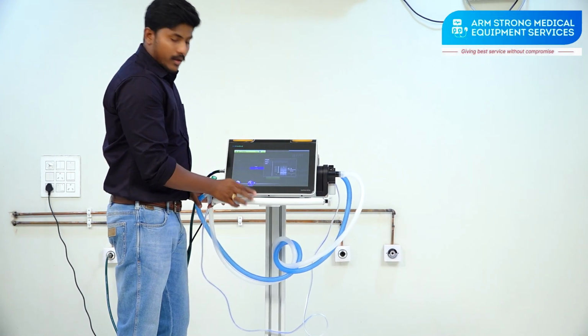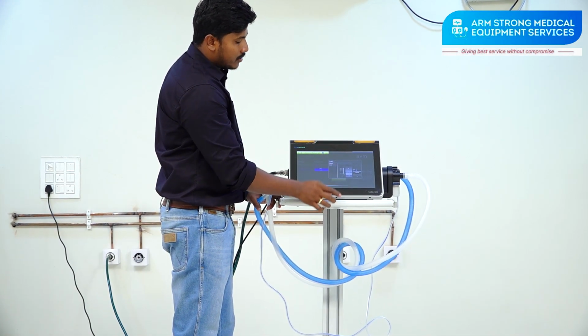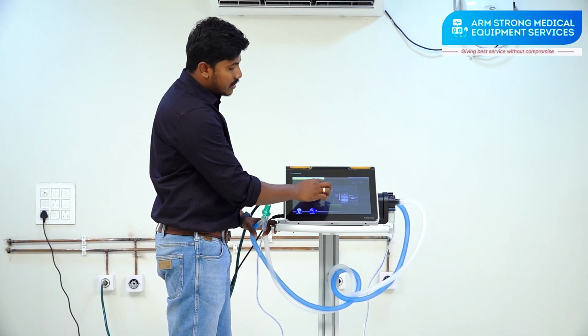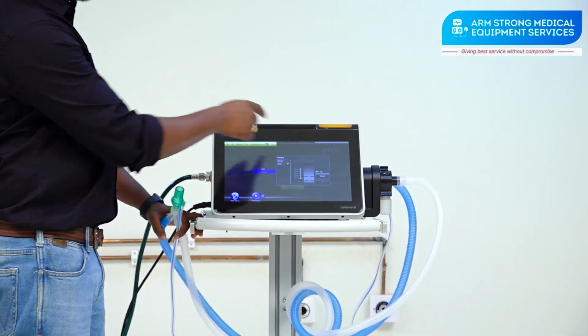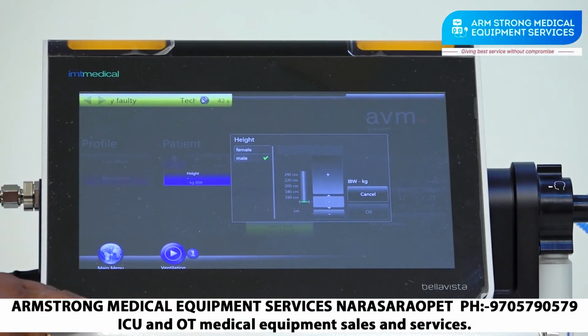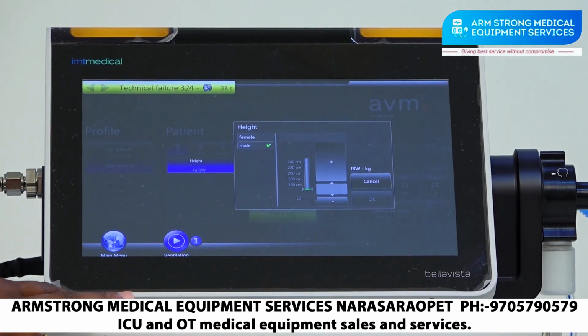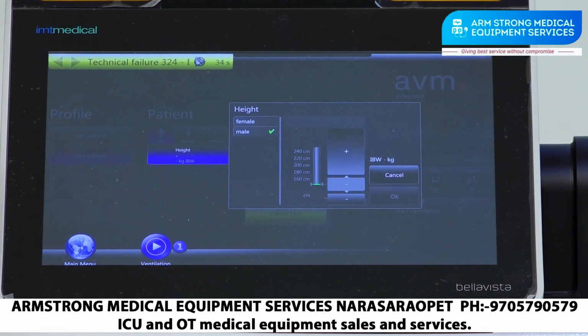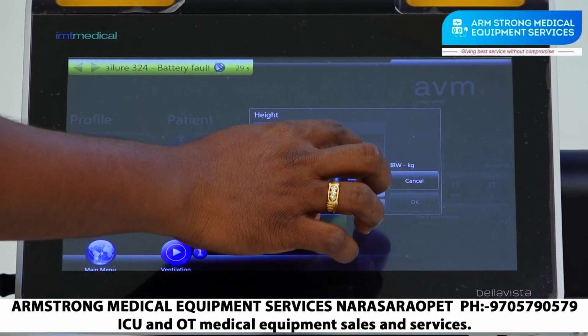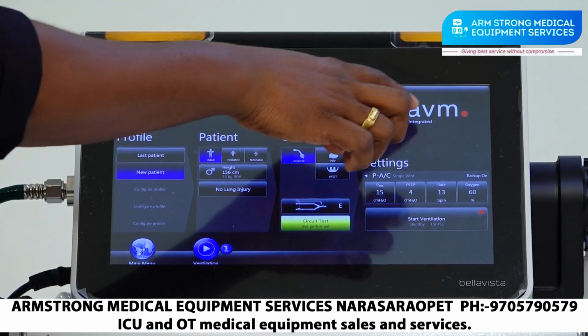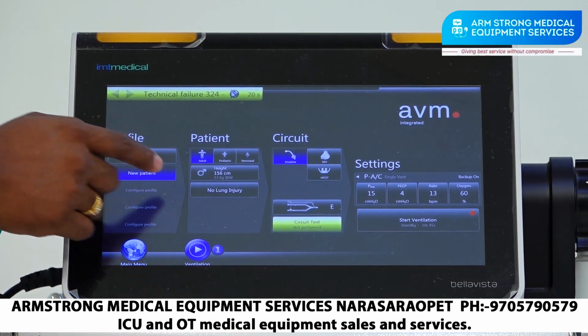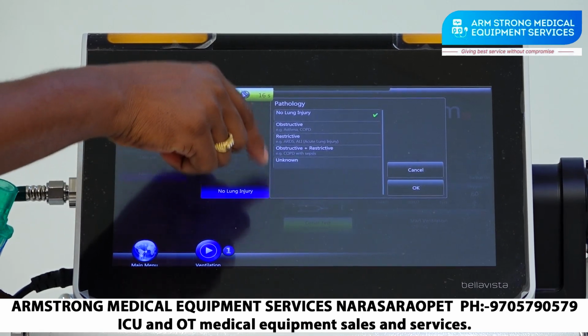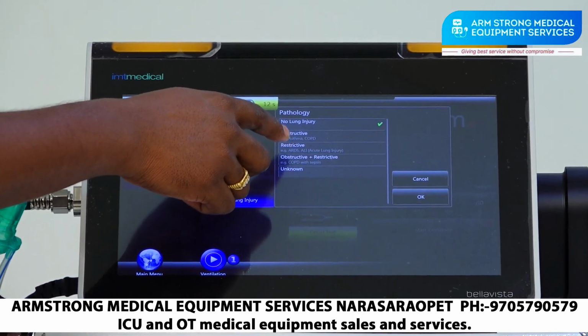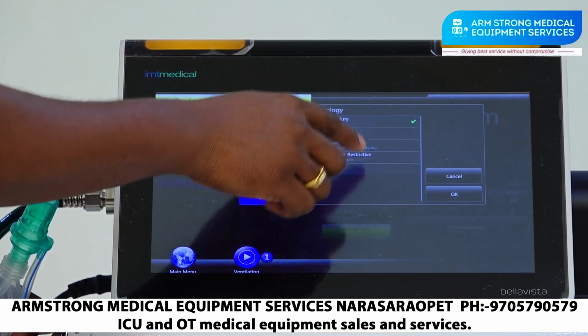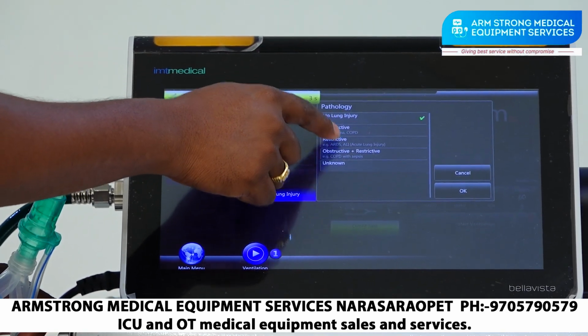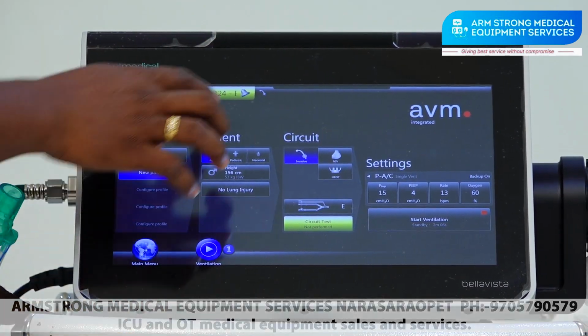In the adult patient category, male and female, both options are there. This selection is there because for tidal volume we have an AVM mode on this ventilator, adaptive ventilation mode. In that mode, if you enter the IBW weight, it will automatically calculate the patient tidal volume and all these settings, and it will ventilate itself. So for that we have IBW also. And here, if you enter the IBW and any lung injury, meaning any patient past history like COPD or any obstructive condition, depending on the patient data history, you just select these things.